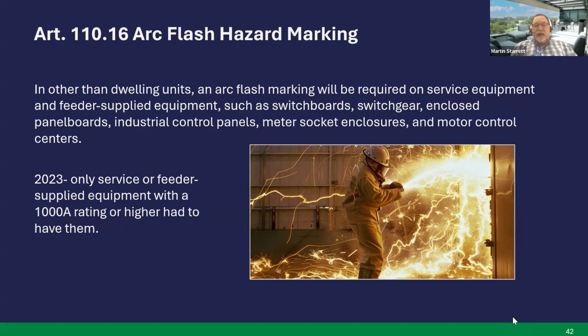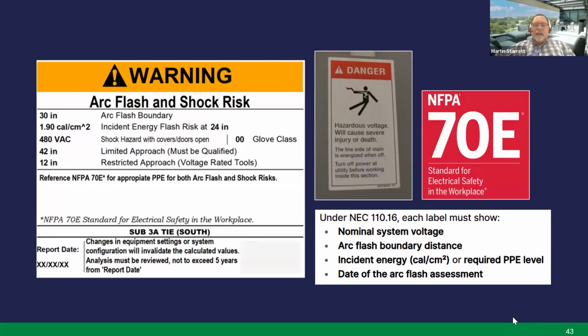But in the 2026 code, in other than dwelling units, that's 1 and 2 family dwellings, an arc flash marking will be required on service equipment and feeder supplied equipment, such as switchboards, switchgear, enclosed panelboards, industrial control panels, meter socket enclosures, and motor control centers. Next slide, please. So this label is going to have the nominal system voltage, the arc flash boundary distance, incident energy or required PPE level, and the date of the arc flash assessment. That'll all have to be on the label.